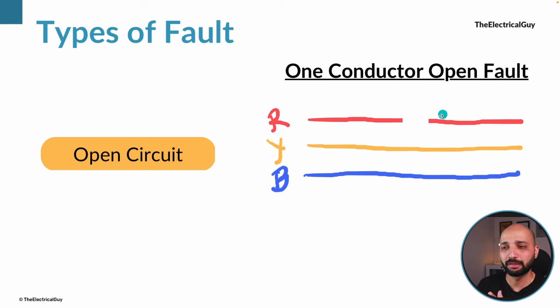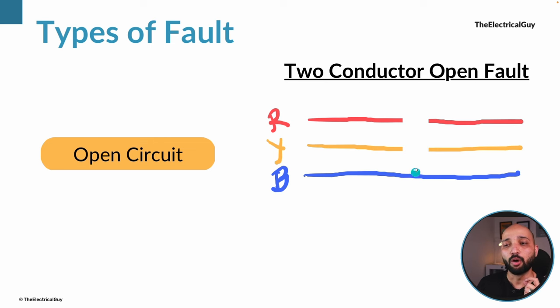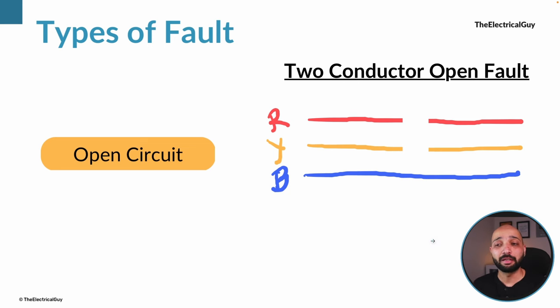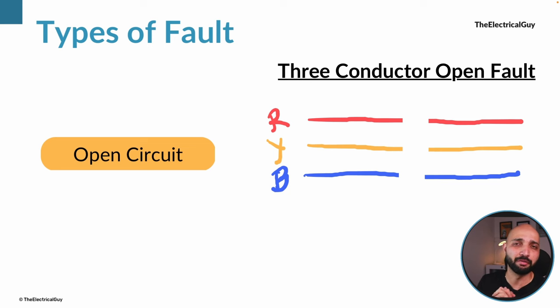In an open circuit, since the conductor is broken, the load of that conductor falls on the Y and B phases, so those two phases will have to carry additional load. As a result, the temperature of the conductor will increase, creating further issues. There can also be a two conductor open fault where two phases are broken, or a three conductor open fault where all three are down. The severity of open circuit faults is not as high as short circuit faults.